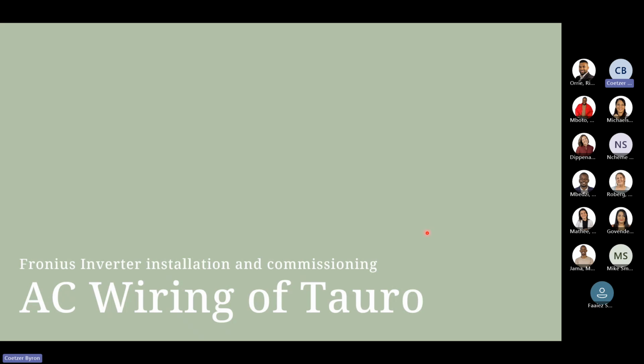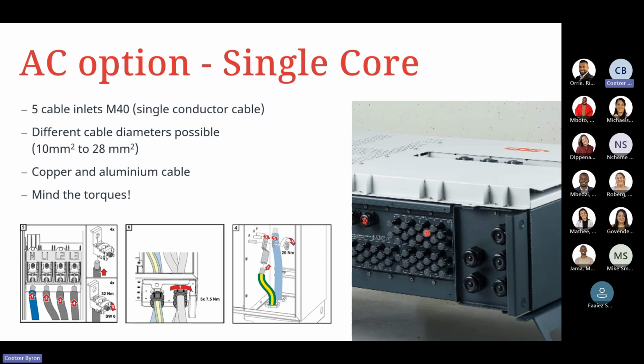On the AC wiring of the Fronius Tauro, there are different options available. This is briefly on the single core. You've got 5 cable inlets on an M40 single conductor cable. Different cable diameters are possible, from 10 mm to 28 mm squared coming in. We can use both copper or aluminium cable, but just keep in mind the torque ratings when using either aluminium or copper cable.